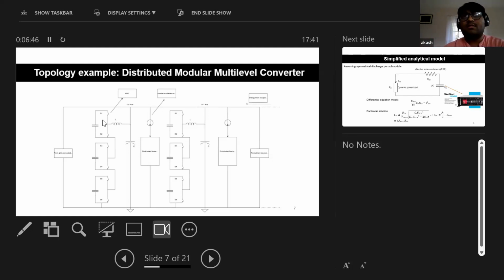So one reason for opting for multi-level or cascaded topologies was because ultracapacitors have an inherent limit in terms of how many you can stack in series because of their internal resistance. You would need a significantly massive heat sink as the internal resistance stacks up. There's also a recommended limit from the suppliers of these ultracapacitors at about 1,500 volts in series.